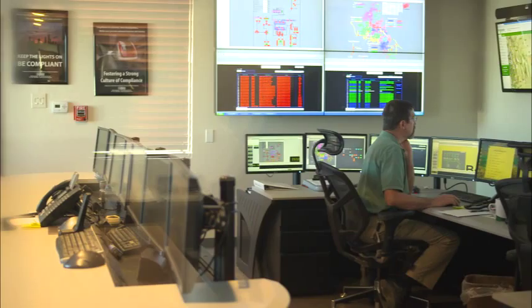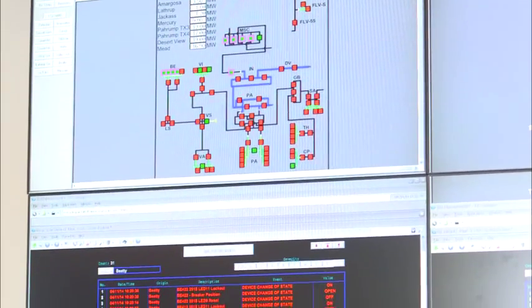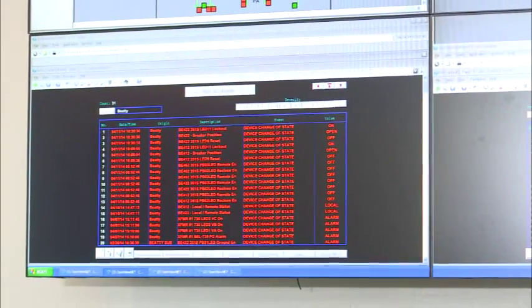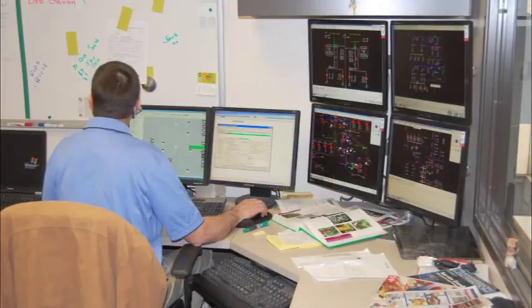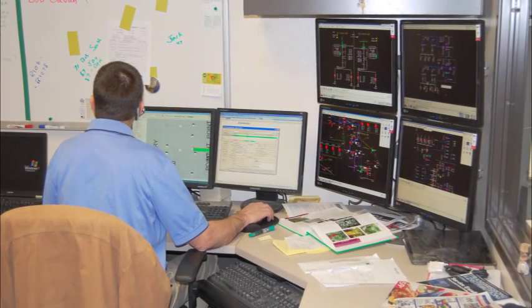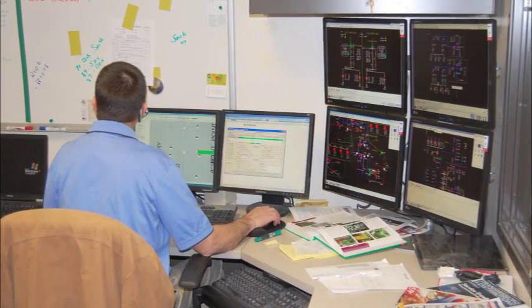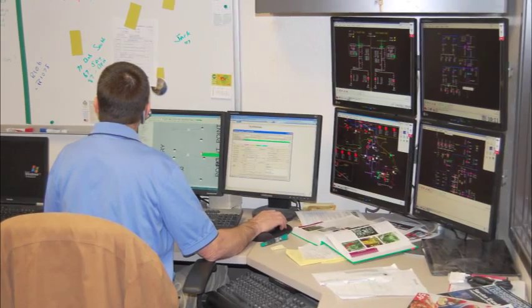Now we have various layers of technology where if a customer calls in with an outage, we can check their meter in a matter of seconds and see if it is or isn't on. We can check the meters around them very quickly, and the software we have will predict what device, what fuse, what transformer, what breaker might be open, so we can very quickly send the crew to that locale and start searching for the problem rather than starting at the phone call and working our way back.